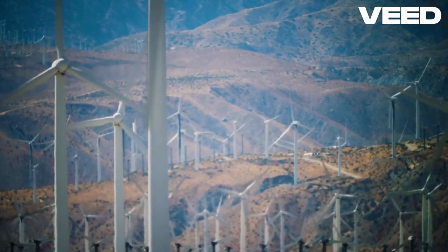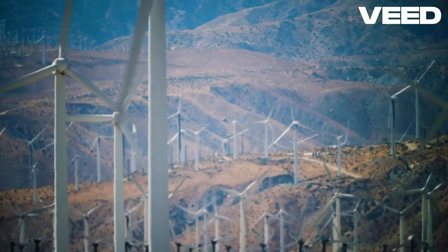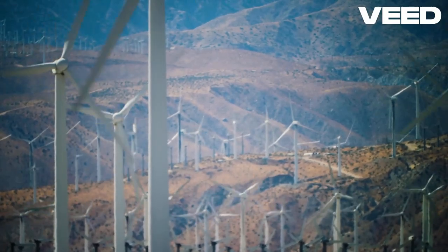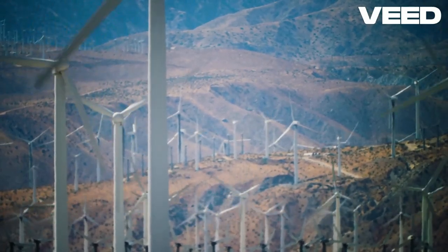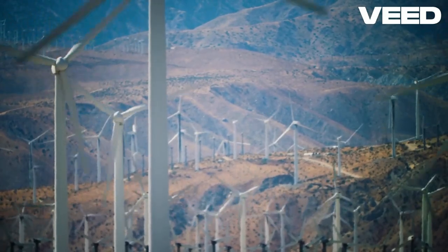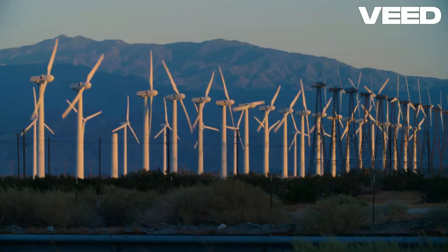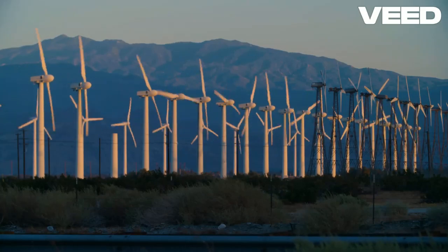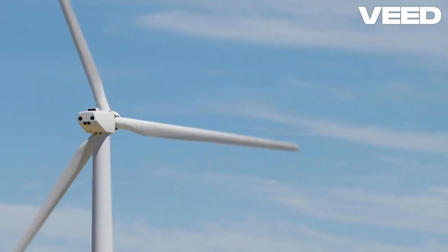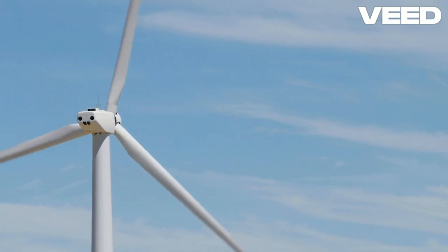To keep this frequency stable, traditional grids have relied heavily on inertia, a property of large, spinning turbines and power plants. These turbines, primarily in coal, gas, or nuclear plants, act as buffers. When there's a sudden mismatch between power supply and demand, their rotational energy absorbs shocks, preventing sharp frequency deviations.